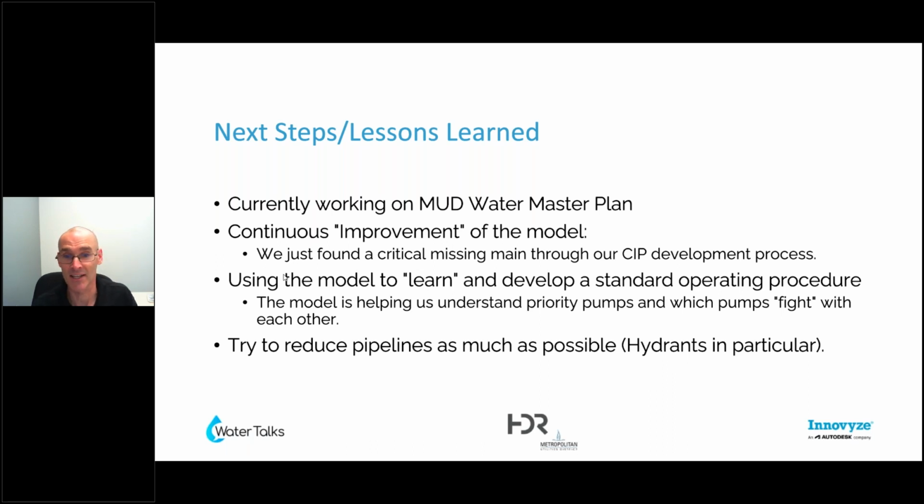I know a lot of times clients want all the hydrants in their models, but I'm starting to lean towards talking them out of that and just modeling the distribution system's ability to deliver to a hydrant, as opposed to modeling each and every hydrant, and that saves a significant amount of runtime. So those are the next steps, lessons learned for us.